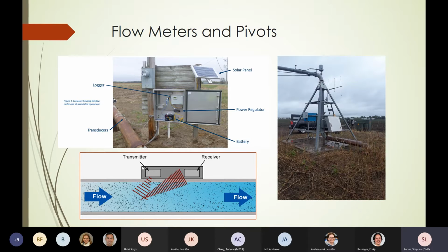The upstream transducer emits this ultrasonic noise, and the downstream transducer receives it, measuring a transit time. There are a few different setups, but you need a certain amount of straight pipe to collect accurate data, so you want the most laminar flow you can find. The longer and straighter the pipe, the better.